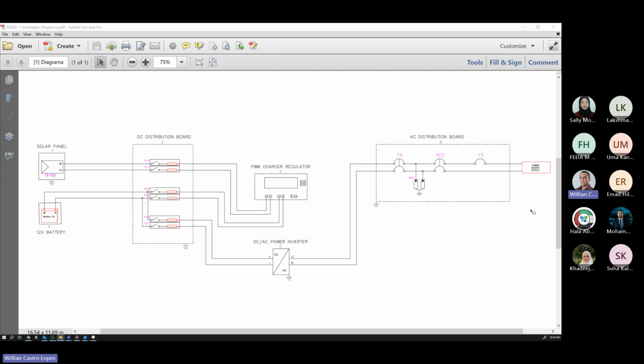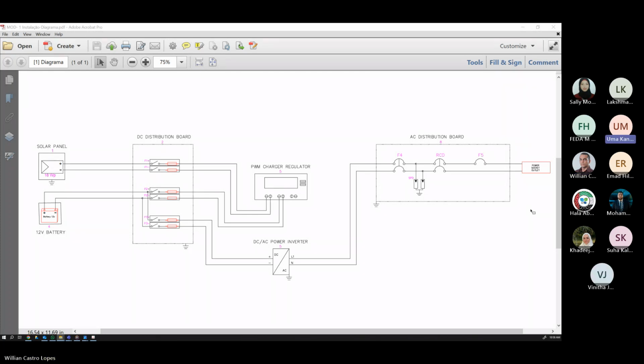This is the sequence. William, I have one question. From the surge protector, if there's any overcurrent in the main wires, is this extra current sent to the earth ground, given your connection to the socket and from the inverter? Yes, but this surge protective device is not to protect against high current, it's voltage. If the voltage increases, the surge protective device acts. But if the current increases, the circuit breaker will act.